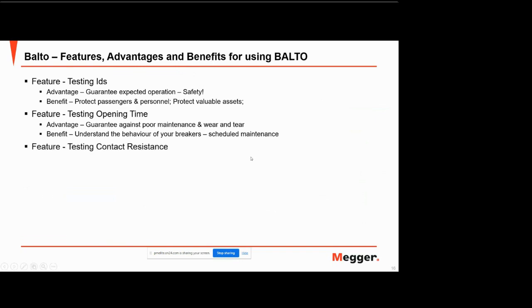We're also testing the contact resistance. So we're detecting any high resistance which could lead to potentially heat generation. We want to make sure that in its operating life, the actual contacts of the breaker aren't causing any high resistance, which could then lead to a potential failure in the future.